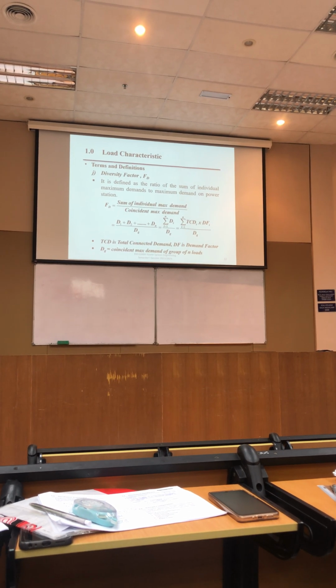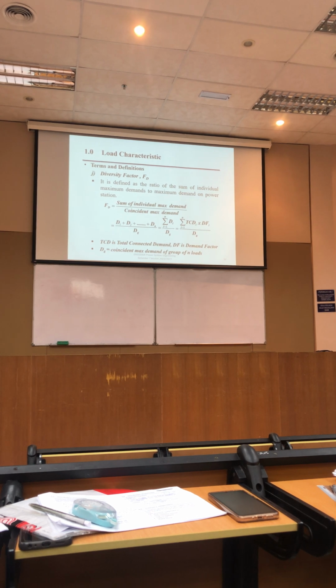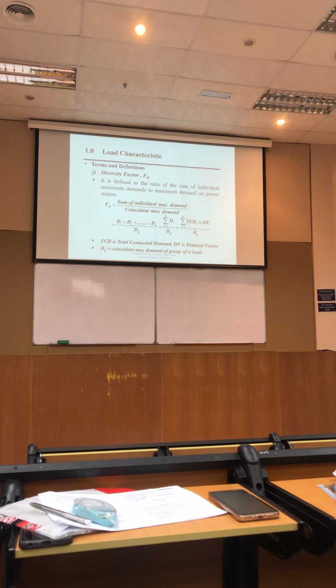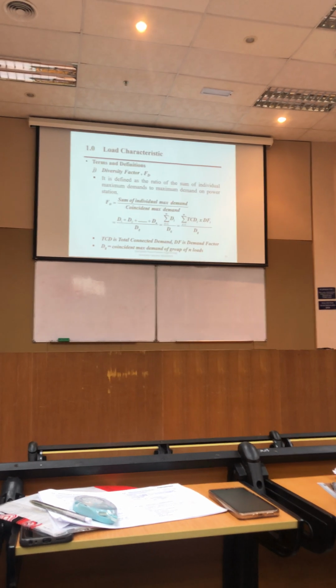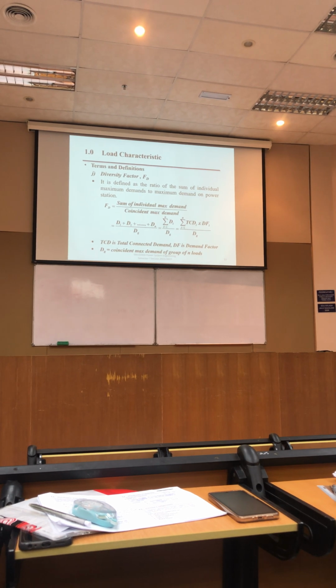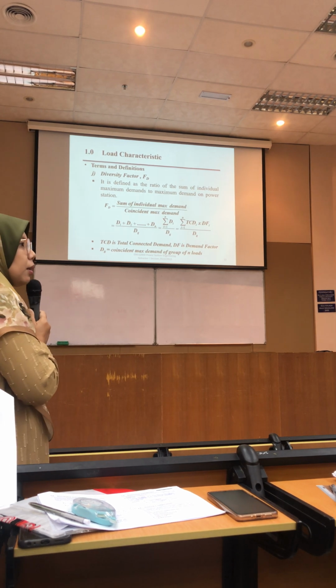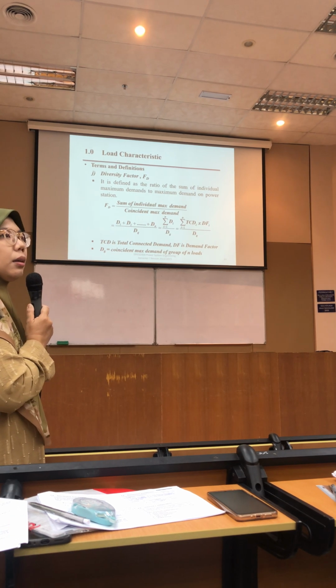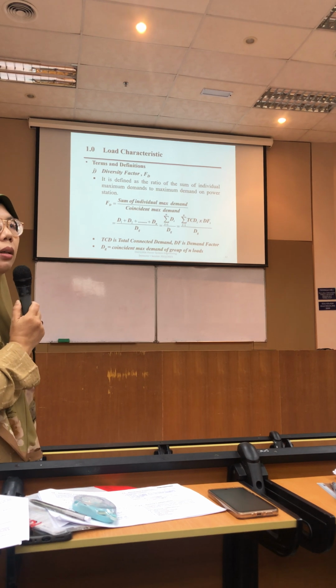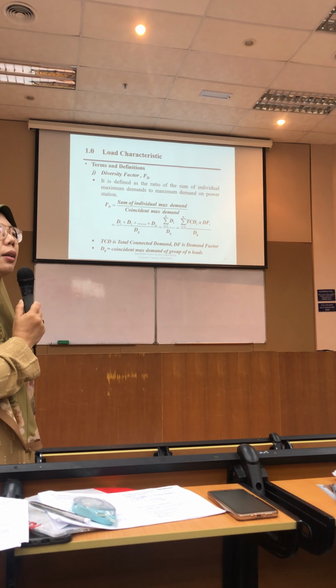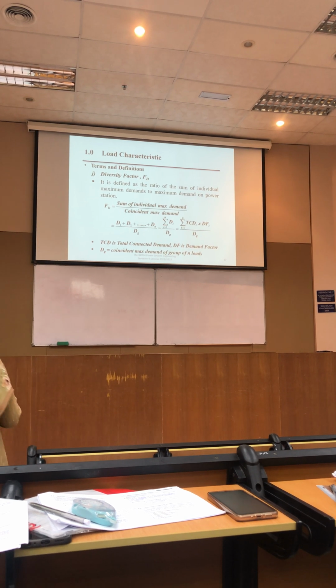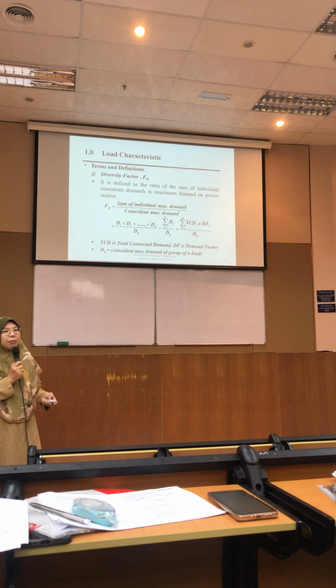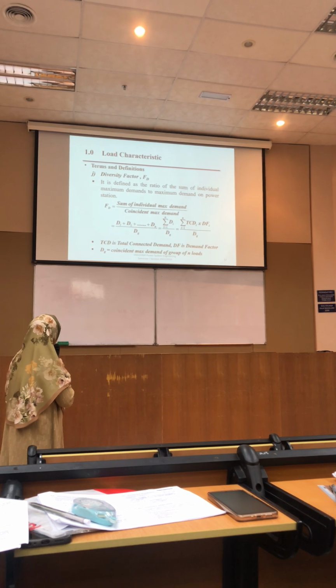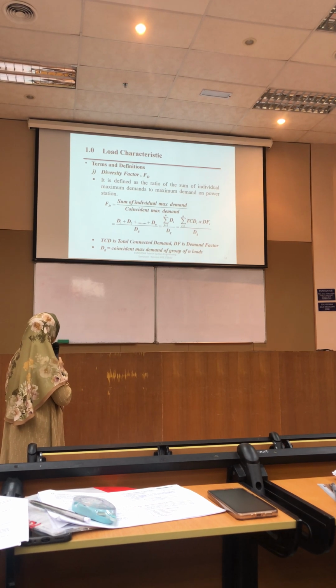So what is the diversity factor? Ratio of sum of individual maximum demand to maximum demand on power station. So each load has their own individual maximum demand. And what is coincident maximum demand, student? Student, what is the coincident maximum demand? The maximum demand of any of your loads, okay, occur at the same time. So that is the coincident maximum demand. Okay, TCD is total connected demand, DF the demand factor, okay, the sum of it divided by the coincident maximum demand group of n loads.